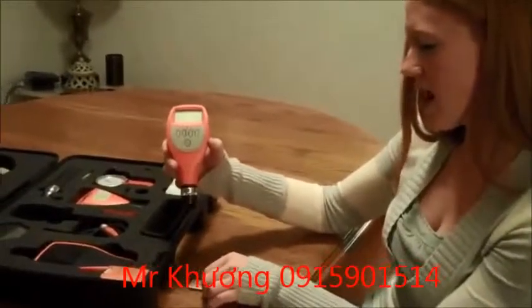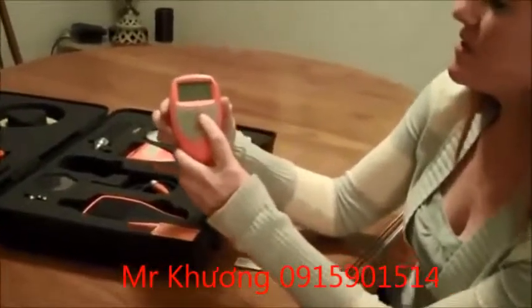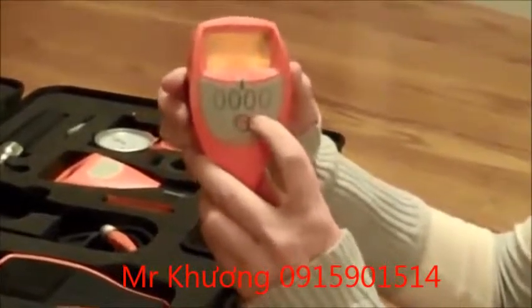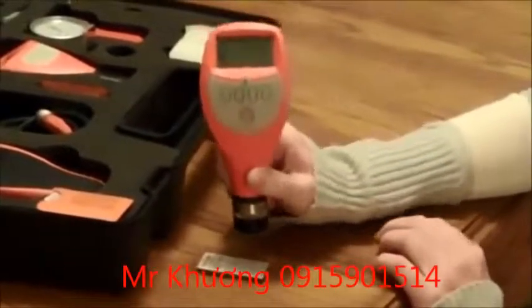Alright, so after I have my shim placed on the base, I'm going to light up and press Cal when the main menu pops up. So I'll press Cal here. Then it will prompt you to place the probe on the Cal standard, which is our shim. So I will test that. It should be right around 9.9. But whatever reading you're getting here, you're going to take several readings and try to get a consistent reading. Take 3 to 5 measurements, make sure it stays the same, and then you're going to dial the gauge in to whatever the Cal standard says.